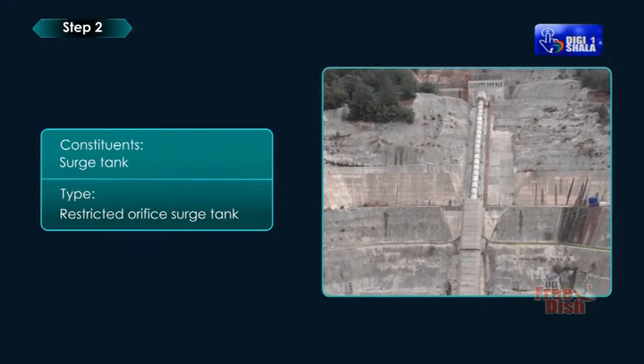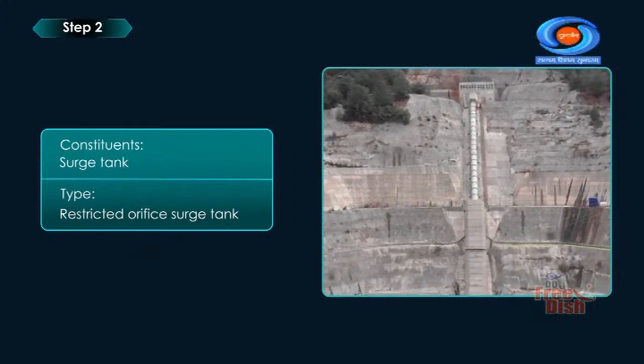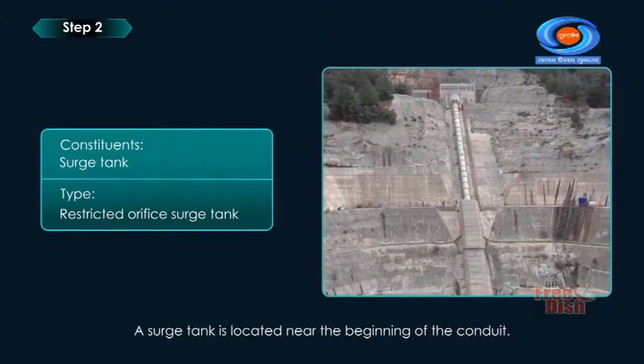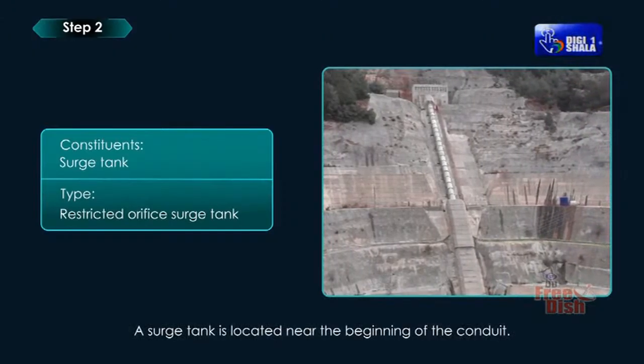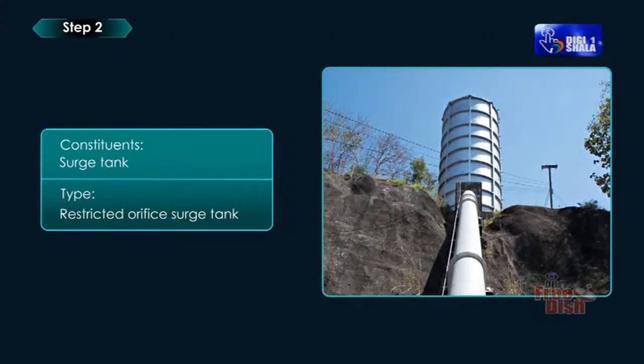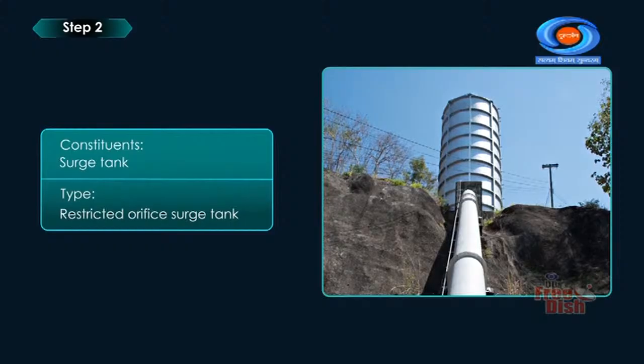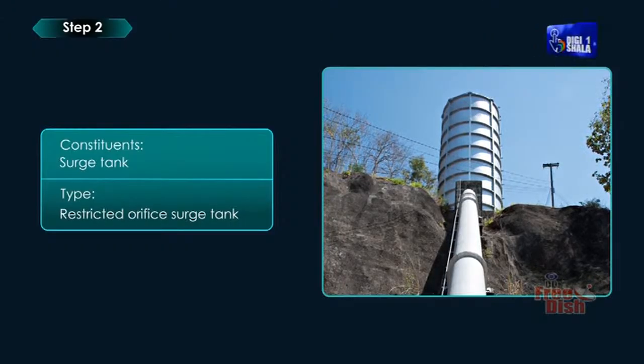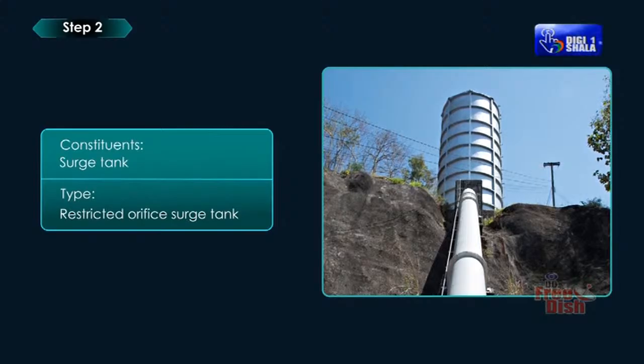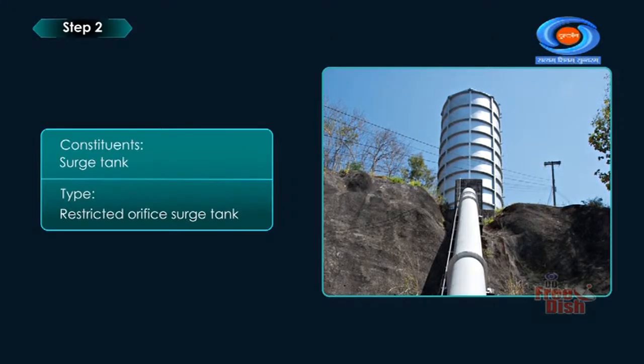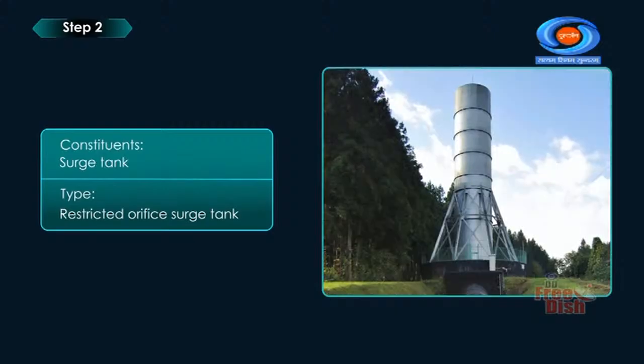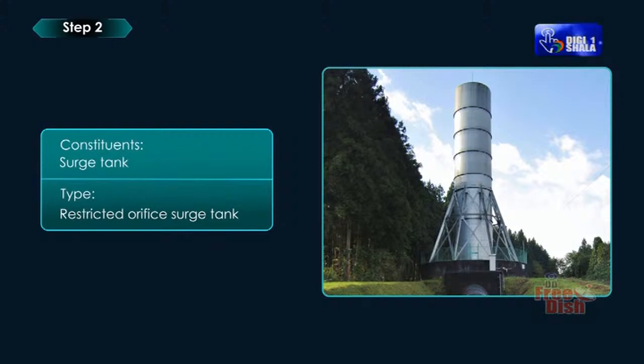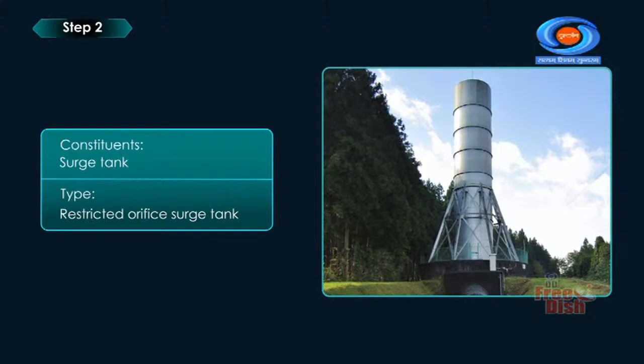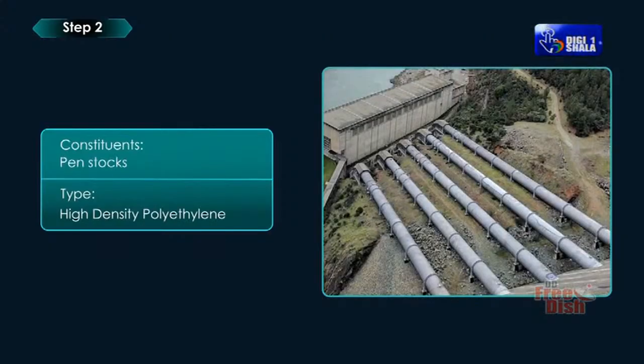Constituents: surge tank. Type: restricted orifice surge tank. Function: a surge tank is located near the beginning of the conduit. When the turbine is running at a steady load, there are no surges in the flow of water through the conduit, which is just sufficient to meet the turbine requirements. However, when the load on the turbine decreases, the governor closes the gates of the turbine, reducing water supply to the turbine. The excess water at the lower end of the conduit rushes back to the surge tank and increases its water level. Thus, the conduit is prevented from bursting. Constituents: penstocks.